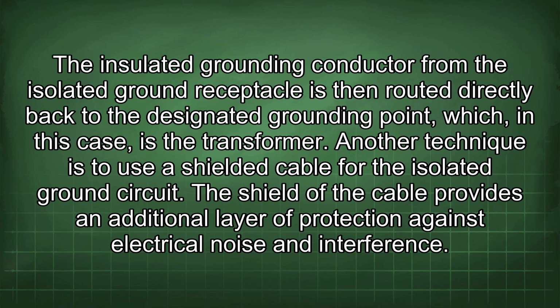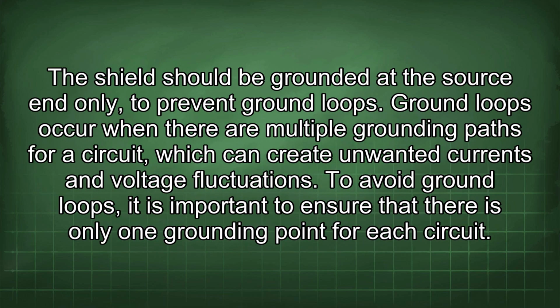Another technique is to use a shielded cable for the isolated ground circuit. The shield of the cable provides an additional layer of protection against electrical noise and interference. The shield should be grounded at the source end only to prevent ground loops. Ground loops occur when there are multiple grounding paths for a circuit, which can create unwanted currents and voltage fluctuations. To avoid ground loops, it is important to ensure that there is only one grounding point for each circuit.